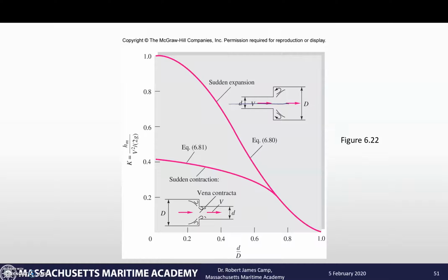So we take a look at this. We've got the expansion from a 2-inch pipe to a 6-inch pipe, so little d over big D. And so that'll give us a third, which is about 33. And so we look here, 33, probably about right there. We read it up, we read it over, and then we can pull out what our value is. It's 0.79. I use the equation to get that. It makes things a little bit easier, but you can use the chart and you'll get roughly the same answer.